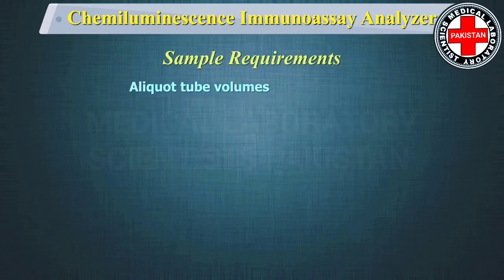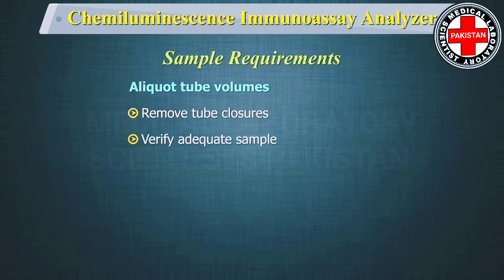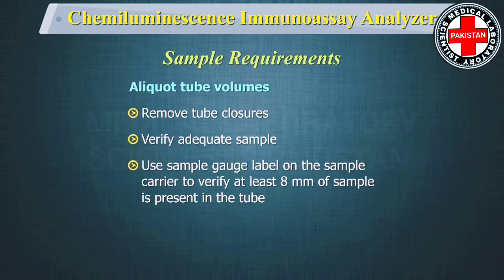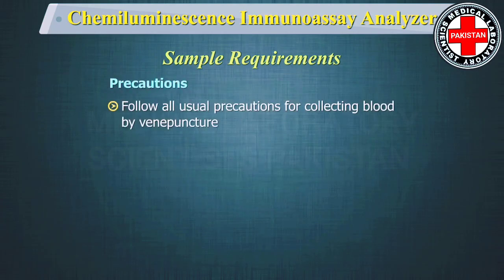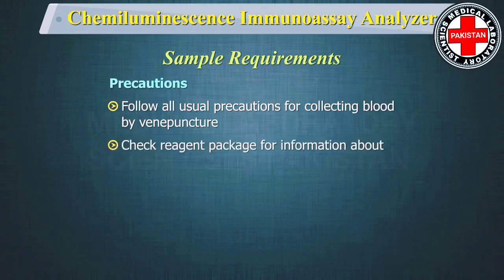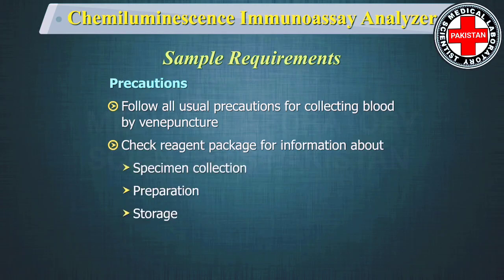When using aliquot tubes, remove any tube closures and verify adequate sample is present in the tube. Use the sample gauge label on the sample carrier to verify that at least 8 mm of sample is present in the tube. Follow all usual precautions for collecting blood by venipuncture to avoid specimen hemolysis. See the reagent package insert for detailed assay-specific information about specimen collection, preparation, and storage.